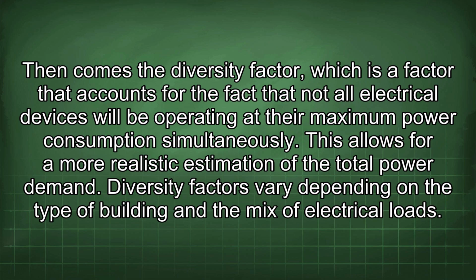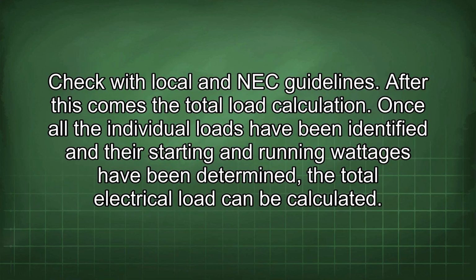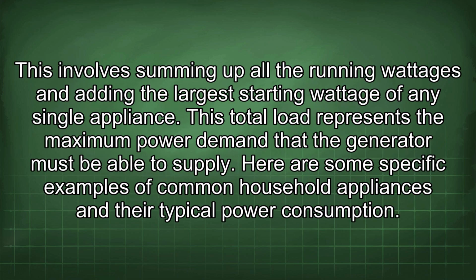Diversity factors vary depending on the type of building and the mix of electrical loads. Check with local and NEC guidelines. After this comes the total load calculation. Once all the individual loads have been identified and their starting and running wattages have been determined, the total electrical load can be calculated. This involves summing up all the running wattages and adding the largest starting wattage of any single appliance. This total load represents the maximum power demand that the generator must be able to supply.